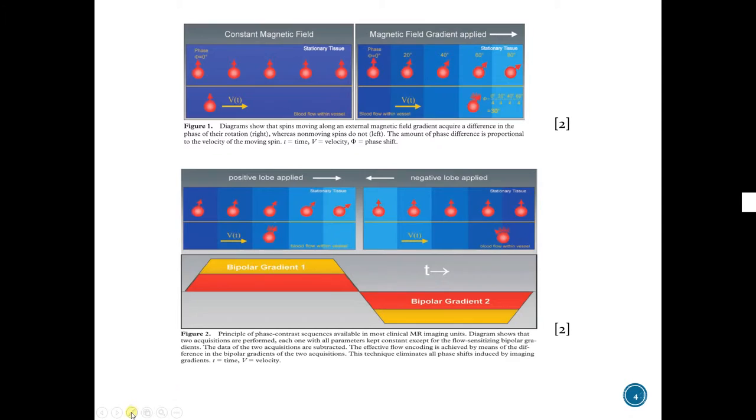So what happens here? Under constant magnetic fields, stationary spins and moving spins have no phase. When magnetic gradient is applied, moving spins and stationary spins acquire phase. In the second figure, bipolar gradients are applied, which I will explain later. After bipolar gradients are applied, stationary spins have no net phase. However, moving spins will have phase shift. The amount of phase shift is proportional to the velocity of the moving spins.